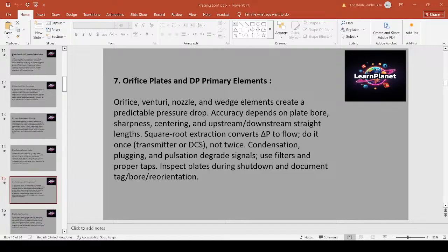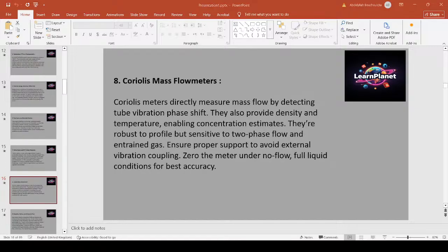Orifice plates create a delta P that scales with velocity squared. Manufacturing tolerances, centering, and edge sharpness matter for accuracy. The beta ratio selection and minimum upstream straight pipe are critical for repeatable results. When using square root extraction, do it once, preferably in transmitters, to avoid double processing errors. Protect orifice taps from condensation and pulsation.